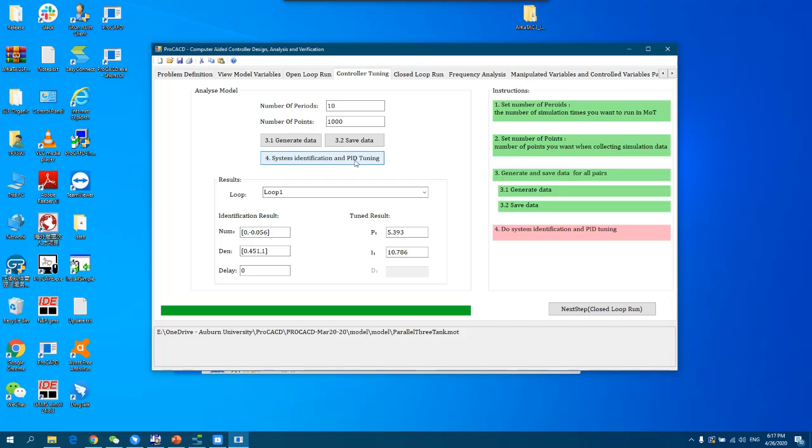Now we will use the transfer function from the system identification task, and we will generate the relative gain matrix. If the diagonal elements are close to 1, that suggests that the pairing of those manipulated and control variables is better with respect to others, and the values which are close to 0.5 mean they have strong interactions and you shouldn't be choosing them. Okay, so I have already clicked it. It will take a bit of time since we have 3 loops here.